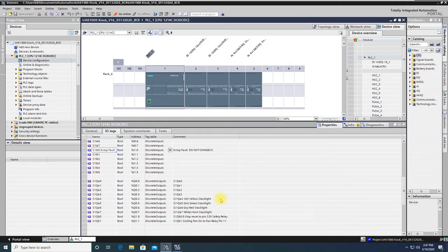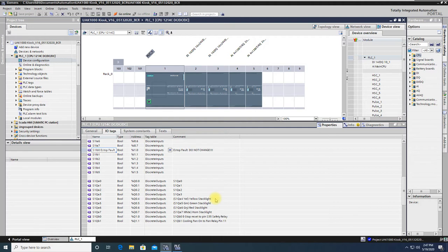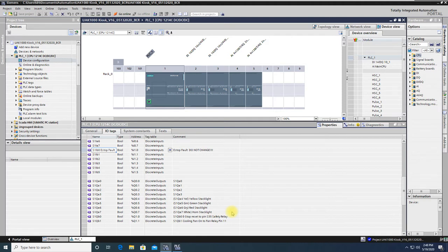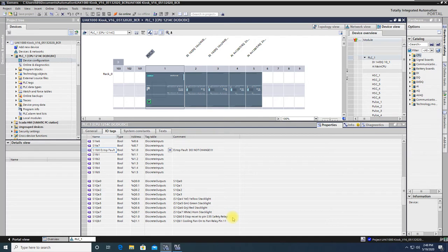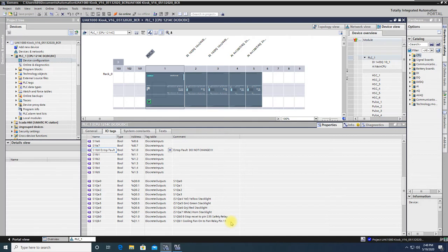Again, we've pre-wired certain of these outputs on the main CPU to an onboard stack light. So if you ever need the yellow, green, or red light to be turned on, you just turn on the appropriate output. There is also a horn on the stack light to annunciate any problems you might have in a machine operation. You can also use an output to reset the safety relay. Should an E-stop condition have occurred, we force it to be reset manually through your program. That would give us a higher SIL rating by doing that. And also, we keep one output as for a cooling fan, so that if you gauge temperature of the cabinet, any high temperature, we can turn on the fan. Once the temperature is safe again, you can turn the fan back off.